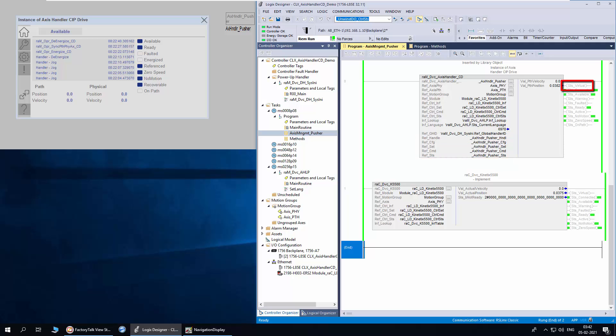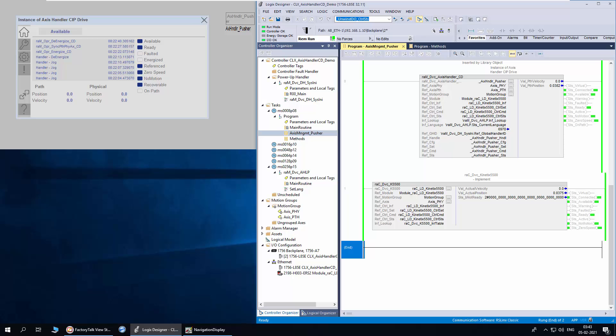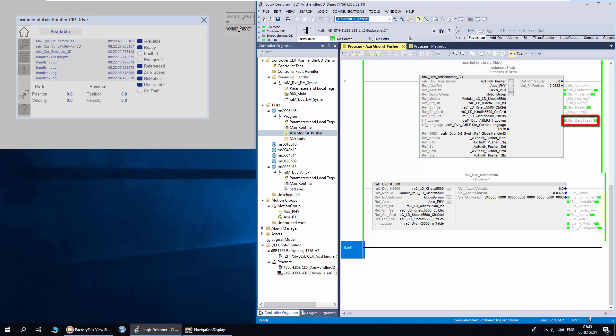The status virtual indicates if the handler is in virtual mode. Connected means the physical device is connected to the controller. Available means the device is not faulted, not inhibited, and the motion group is synced. Warning means there is an active warning in the device. Faulted means the device is faulted. Ready means the device is connected, configured, and ready to receive user commands. Active means the device power structure is enabled. No motion means the device is active with no active motion instructions. Zero speed means the axis velocity is within the user-specified standstill limit. On path means the physical axis is geared to its path axis and its command position is matched to the path axis position.